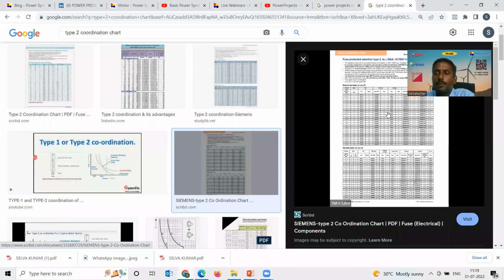And type 2 coordination has a clear chart for what capacity motor needs what protection device to be selected. One interesting fact you need to understand: nowadays motors, especially at low voltage, are extremely high energy efficient. Energy efficient motors come with a higher X by R ratio, and they also come with higher starting current. You might be aware we are talking about energy efficiency very rigorously.